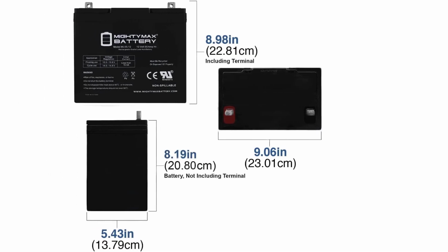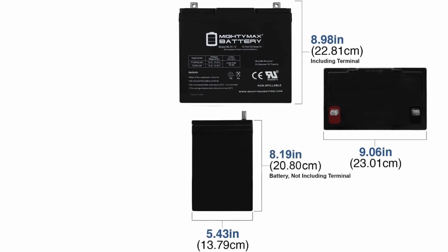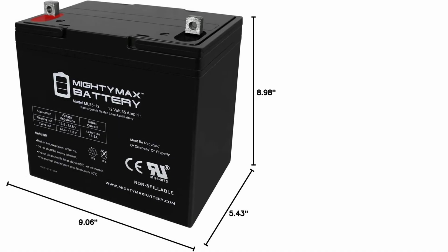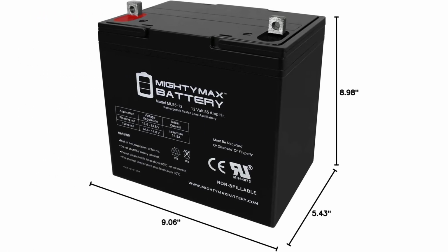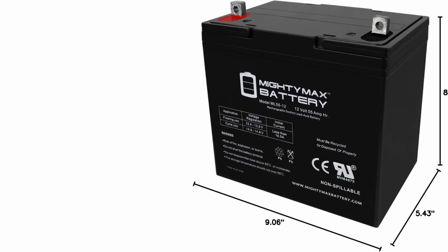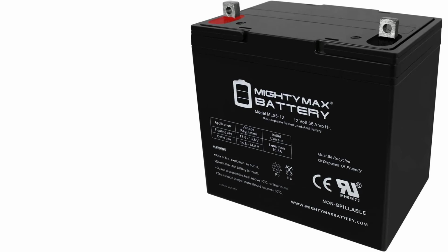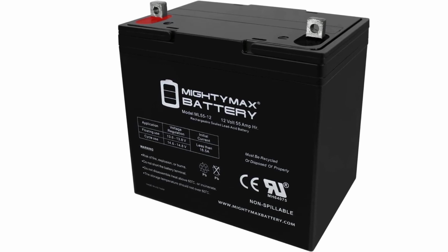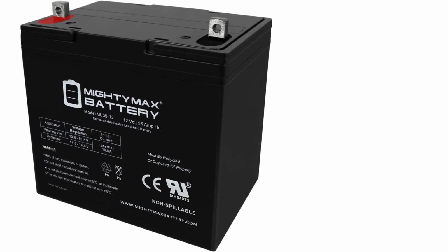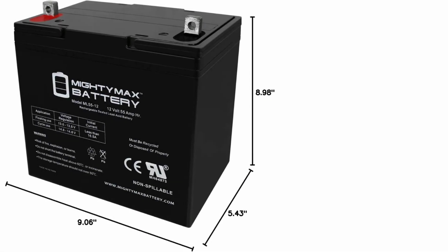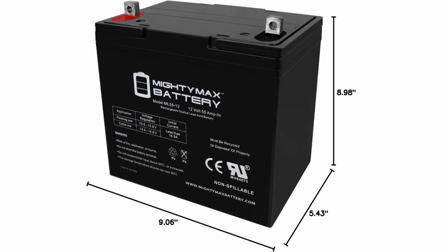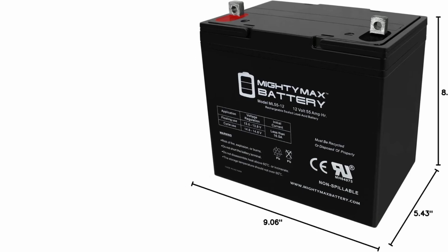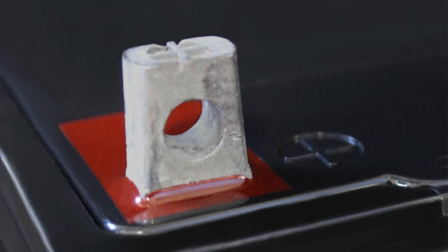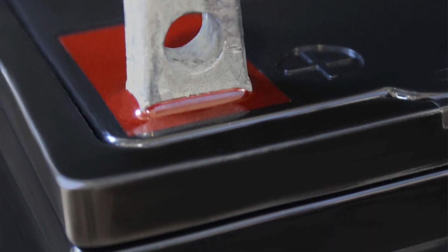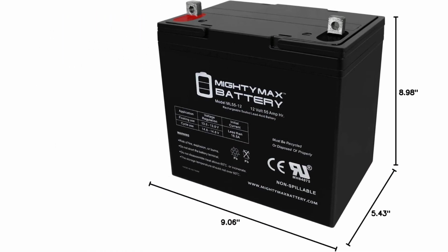The battery measures approximately 9.06 x 5.43 x 8.98 inches and provides a high discharge rate with reliable performance across a wide range of temperatures. It uses a heavy-duty calcium alloy grid for durability, and its recommended charging parameters are 14.4 to 14.7 V for cyclic use, 13.6 to 13.8 V for float use. With low internal resistance and long service life, the ML55-12 delivers consistent power for medium demand loads. While it is relatively heavy and does not include mounting hardware, it offers a cost-effective, high-performance option for portable power applications and comes with a 1-year warranty.